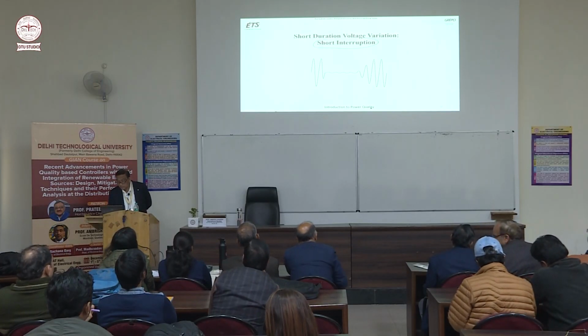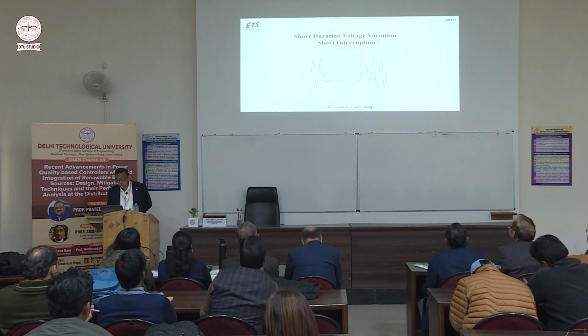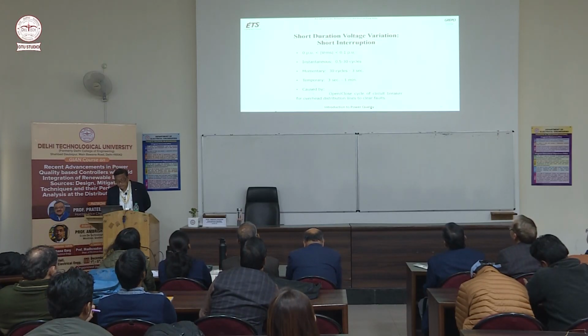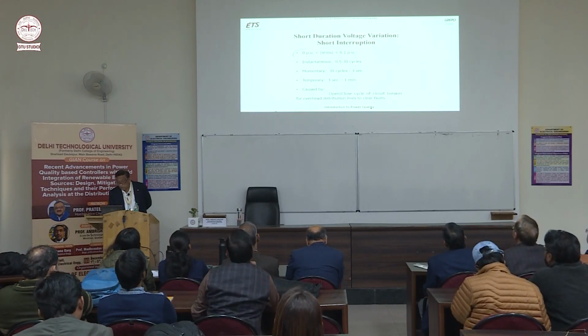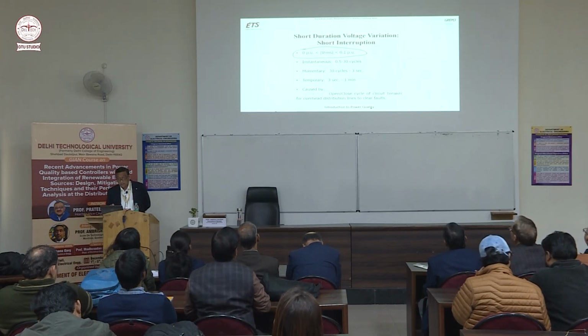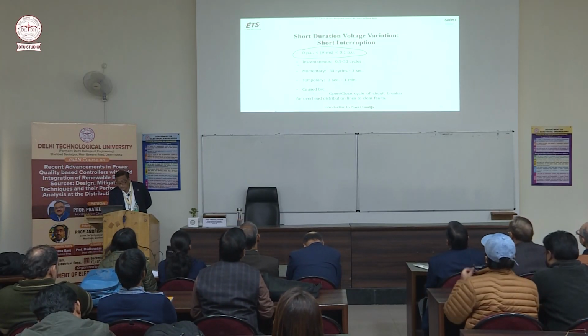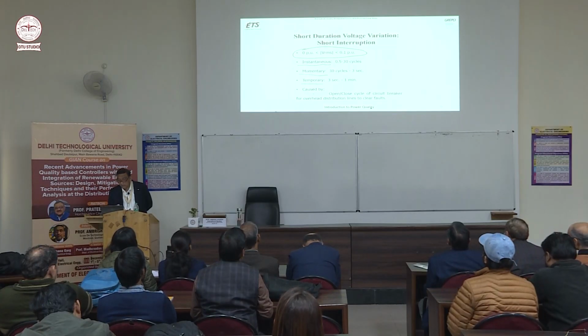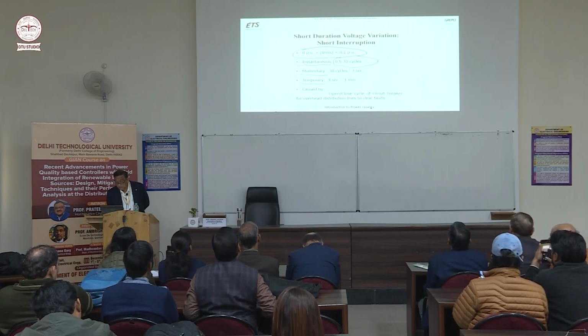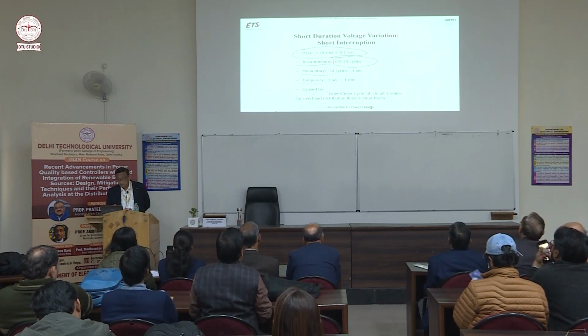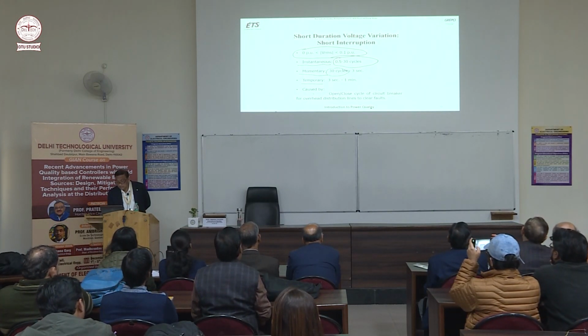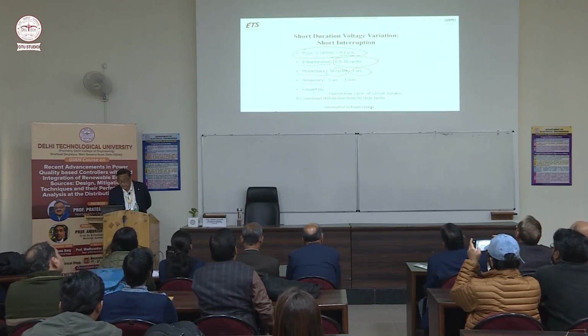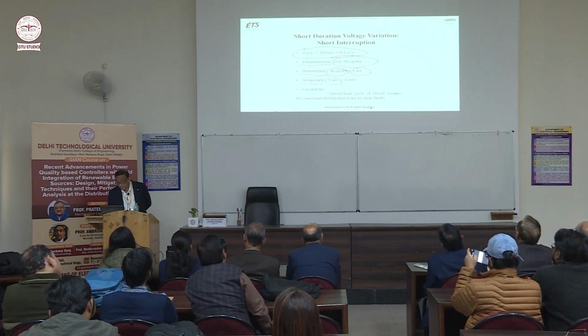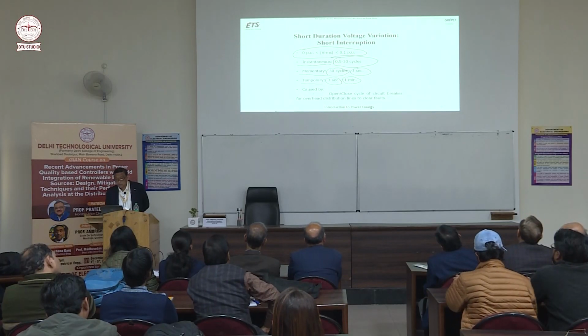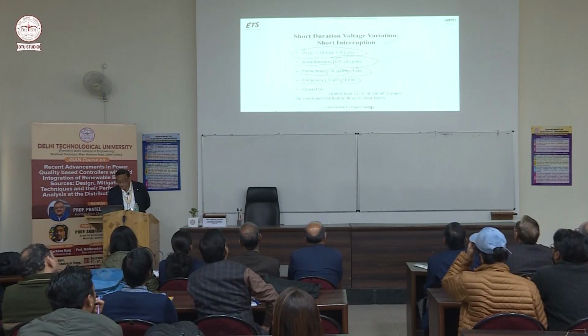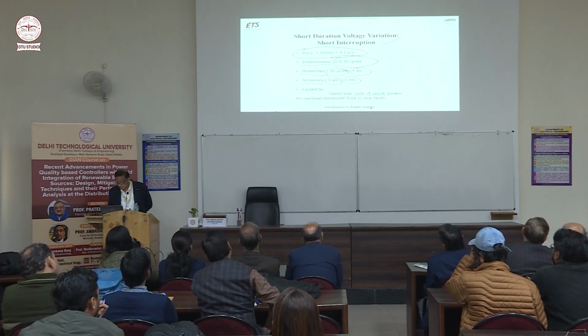Short interruptions: for a certain period of time, there is no electricity. This is the short interruption. The voltage is between 0 pu and 0.1 pu. There are three types: instantaneous, momentary, and temporary. Instantaneous if it is between half a cycle and 30 cycles. Momentary if it is between 30 cycles and 3 seconds. And temporary if it is more than 3 seconds and less than 1 minute. So these are short interruptions caused by the open-close cycle of a circuit breaker on an overhead transmission or distribution line.